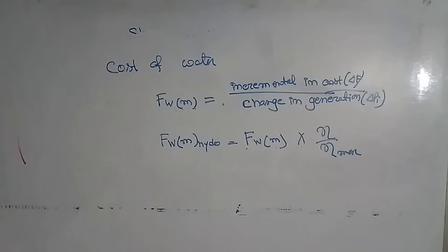Thus, the incremental water value is given by lambda j into delta P. On the other hand, if energy requirement increases from P to P plus delta P, the hydro system may be assigned to give this energy, while its water flow increases from Q to Q plus delta Q. The incremental water value is then mu j into delta Q amount of money in each hour.